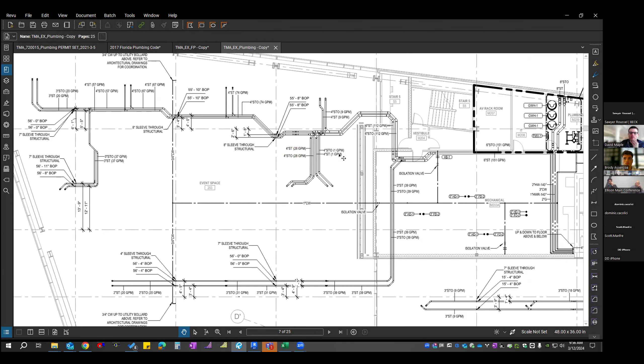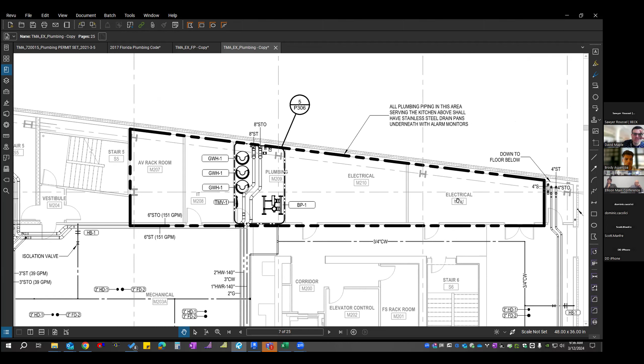Here on the second floor mezzanine we have electrical room, plumbing, IT, AV, mostly electrical and IT, and directly above this is a kitchen. So we have a general note that any piping serving the kitchen above, we try to coordinate so it's routed center of room or exits as quickly as possible, not routed directly over any panels. We want to provide drain pans underneath any piping with alarm monitors if there's some sort of leak detected.